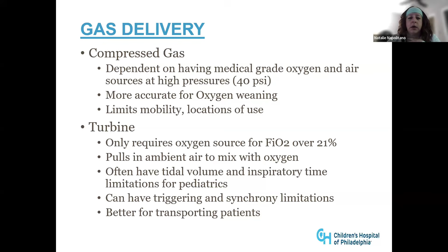And some of them are very good, particularly for adults, but for children, you really have to take a look at how well their triggering is and their synchrony and your limits on pressure and tidal volume, mostly for the lower limit, when you're choosing one of these. You also really need to take a look at their battery power, so the oxygen source, as well as air and your electricity sources, and how often you're going to have good stable electricity, so that you can see how long the battery is. Some of these batteries are very long lasting and are hot swappable, which is really nice.